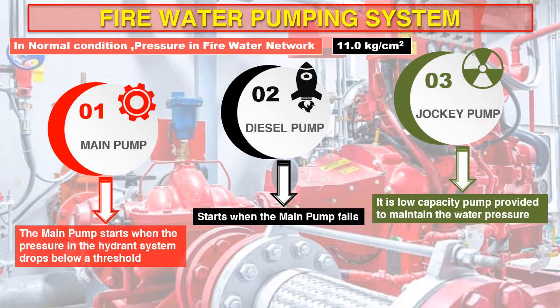In normal condition, the pressure in the fire water network will be kept at 11 kg/cm². In case of any minor leakage, the pressure will gradually drop, which will be sensed via a pressure switch and will operate the selected jockey pump automatically. Once the system pressure is maintained, the jockey pump will stop automatically. When hydrants or deluge valves are operated in a fire, the pressure will drastically drop, thereby operating the fire pump sequentially. The jockey pumps and fire pumps are interlocked such that the jockey pump stops as soon as the fire pump is started.